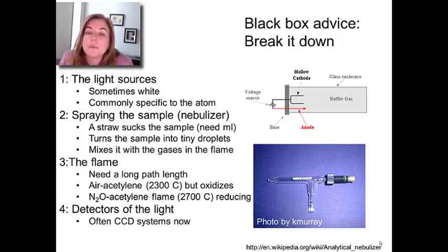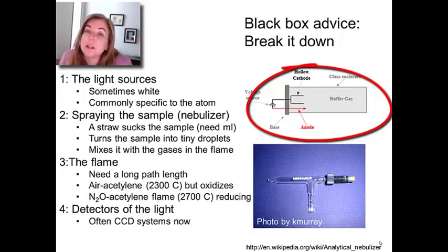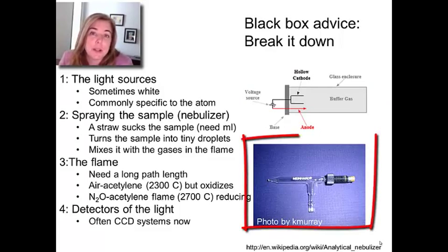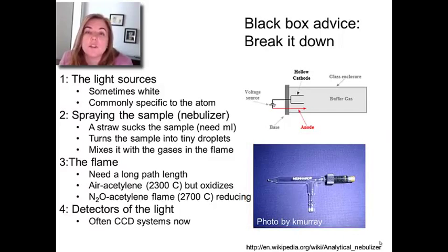Here are some diagrams. You can see a hollow cathode lamp, which has a cup of the metal you want to detect. Because you put a voltage across it, you get a vapor that's generated, which emits light that you're using as your light source. At the bottom is a nebulizer, the fancy spray bottle. It looks more complicated than that. Nebulizers are really important because you need to put things into the gas phase. If you don't have a good nebulizer, you might suck up 50 mils of sample, but how many atoms made it into the flame in vapor phase in their ground state? The nebulizer controls the sampling efficiency. If that's poor, you have to go through a lot of material to detect it. New nebulizer designs are an important research goal for atomic spectroscopy.